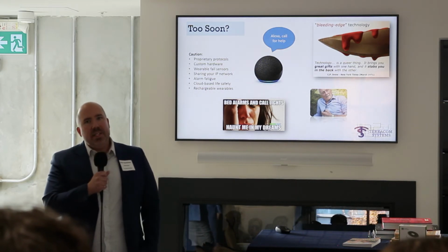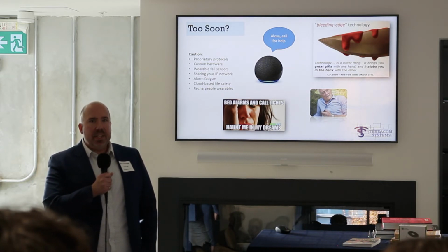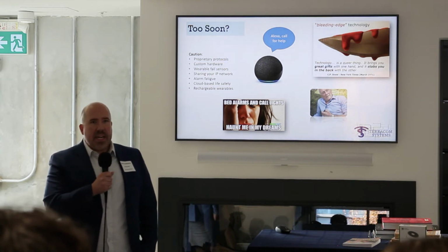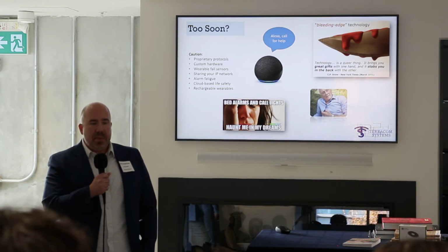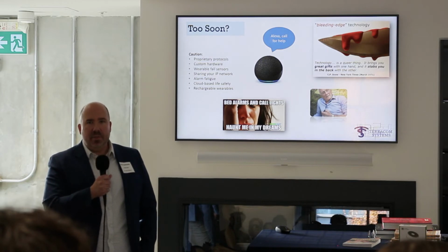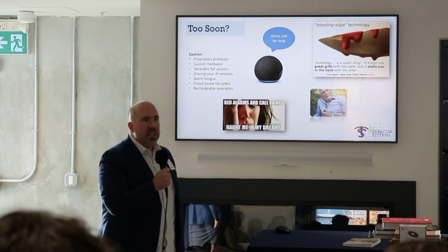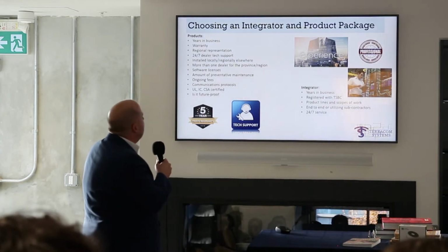And that's not easy. You really have to have a reputable IT contractor or IT employees that can actually set up those rules. They're called quality of service settings, where you can actually prioritize one thing over another. Some sites even ask us to completely physically separate the network. We would have our own network physically just based for all of our life safety stuff, and then they would use their other network for their data, their Zoom, their Wi-Fi, Netflix, so be it. So that's one thing in particular that you got to watch out for, because nowadays everything is going network based.